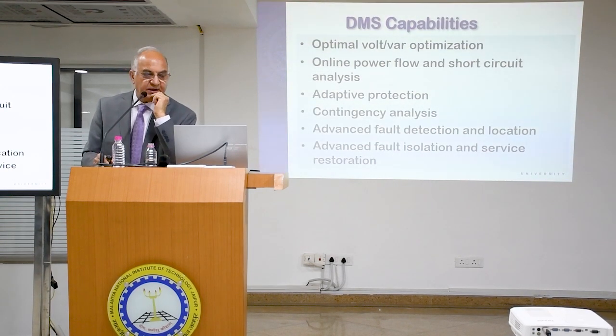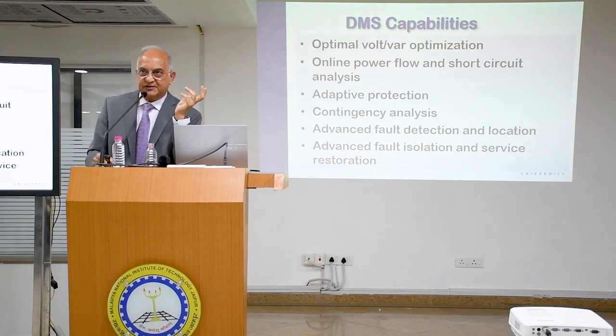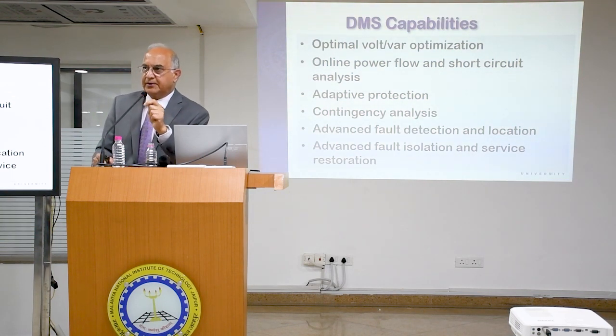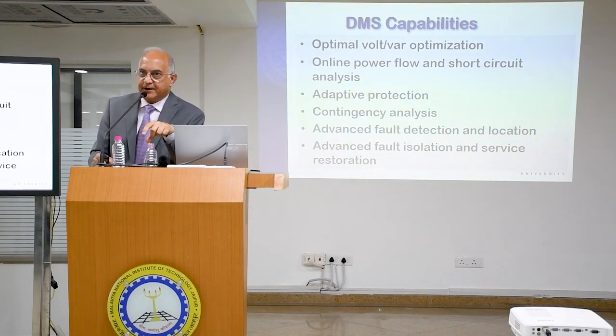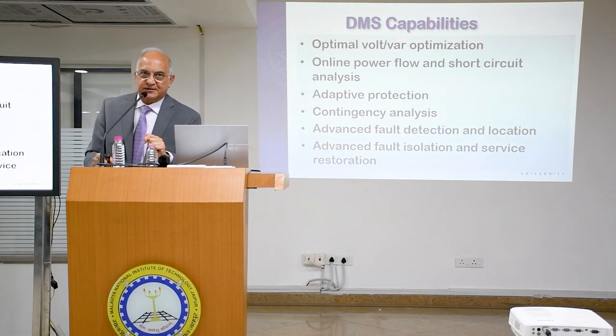What are the DMS capabilities? We can do network-wide optimization, because voltage is dependent on reactive power. If you put more reactive power into the system, the voltage increases; if you have less reactive power, the voltage decreases. So with proper management, you can optimize voltage better.